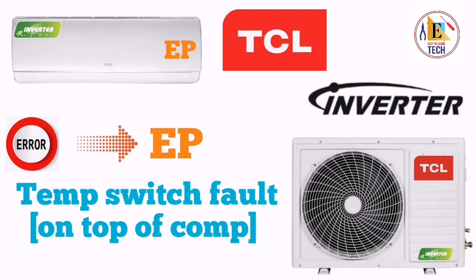And again if you start the unit, and again if you are getting the same problem, then you have to check the ventilation of your outdoor unit, if the ventilation is good or not. If the ventilation is not good, then you have to make the ventilation good, and you have to install it in a proper place where the ventilation is free. And again if you are getting the same problem after doing this, then you have to check if the temperature of your compressor is high or not.